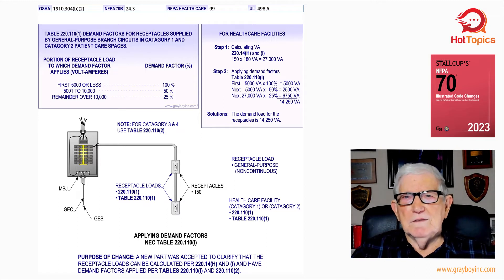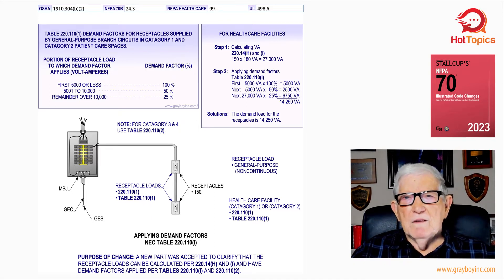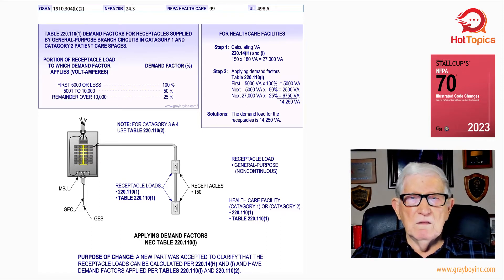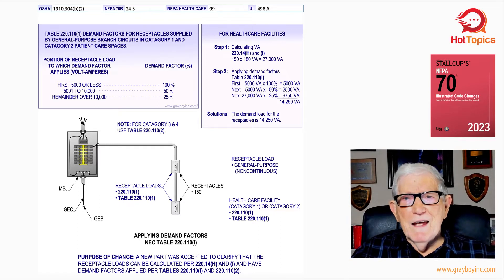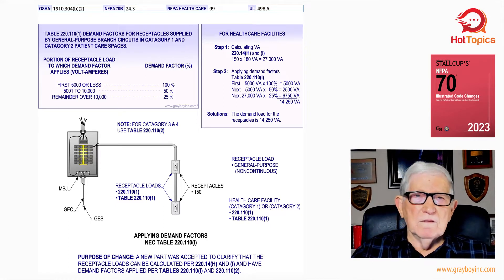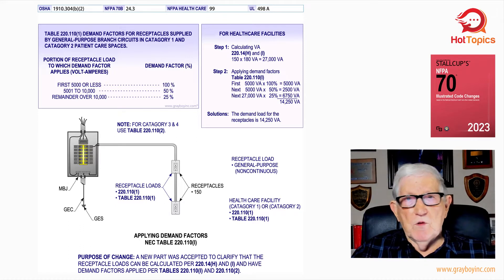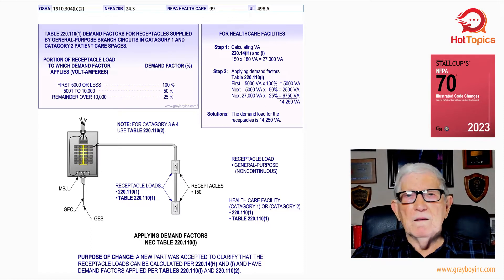For example, look at the calculation here. Per 220.14H and I, 150 receptacles at 180 VA would come up to 27,000 VA — that's step one. Step two, applying the demand factors of table 220.110.1: first 5,000 at 100% — so 5,000 right across the board. The next 5,000 at 50%, we'd come up with 2,500. Then anything over 10,000 — and our total is 27,000 — we'd take 25%. Our demands would be: 100% no demand, 50% demand, 25% demand, and when you total those values, we come up with 14,250.